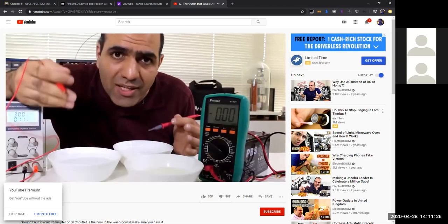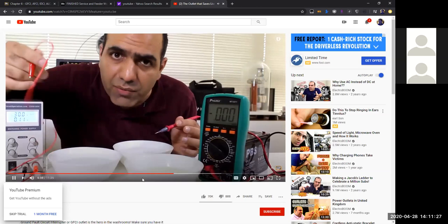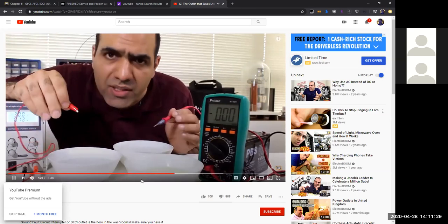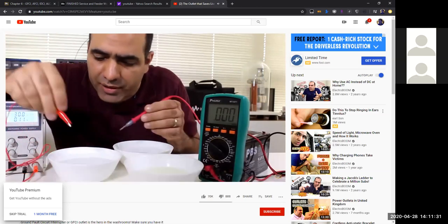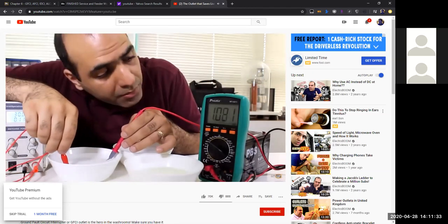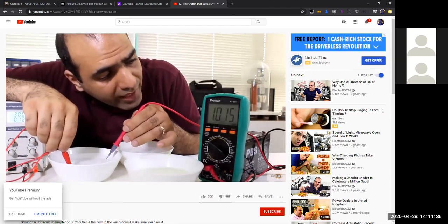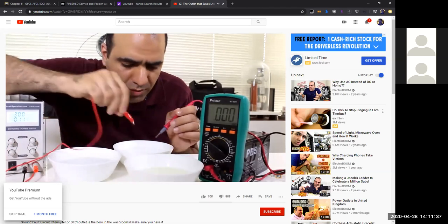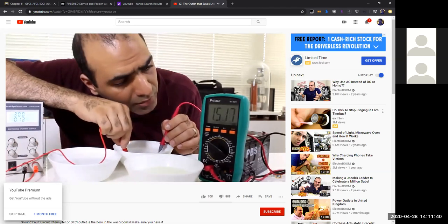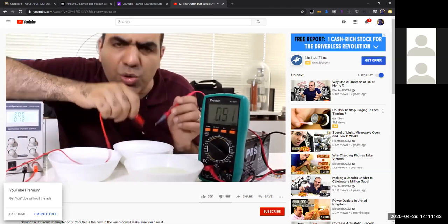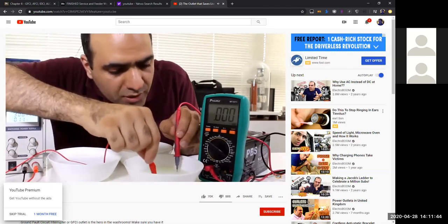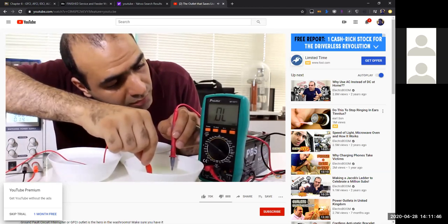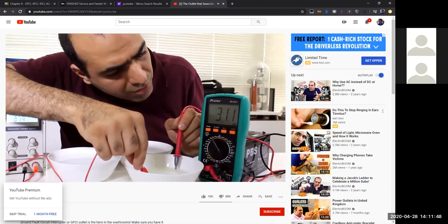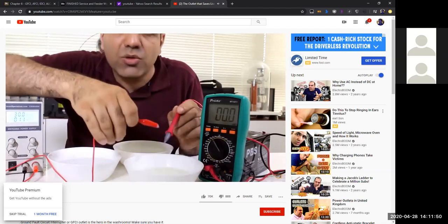Let's measure the resistances by running some current through them with my 30 volt DC. We know any resistance below 24 kilo ohms triggers the breaker. Cold water is around 1 milliamp, so 30 kilo ohms. Hot tap water is 1.5 milliamps or 20 kilo ohms, so it triggers. The soapy water is around 30 milliamps, which means around 1 kilo ohm.